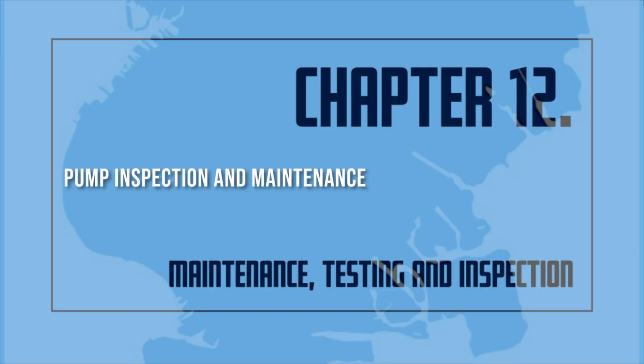Pump inspection and maintenance. In order to ensure the reliable operation of the pump in case of an emergency, regular inspections and maintenance shall be conducted by the certificate of fitness holder. The pump should be activated each week and run for 10 minutes in accordance with the manufacturer specifications to ensure that it is functioning properly. When the pump is in operation, a small water leak on the pump packing is desirable and should not be considered a malfunction.